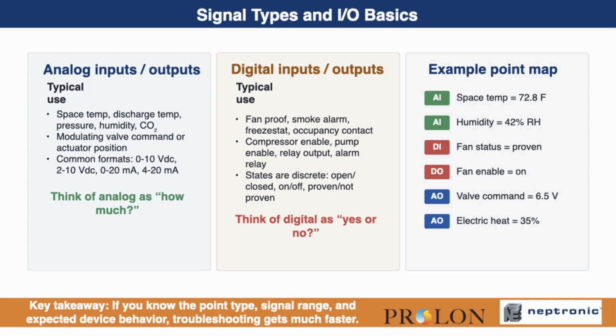In a chilled water air handler application, chilled water supply temperature can be an analog input. A chilled water control valve command can be an analog output. A freezestat can be a digital input, and a pump enable can be a digital output. In a VFD supply fan application, the VFD speed command is usually an analog output, while the run command is digital. These examples help the audience connect AI, AO, DI, and DO to real equipment behavior in the field.